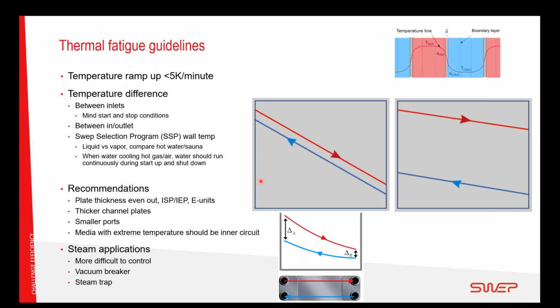We have this defined within our SWEP selection software, which is the SSP, which is used for dimensioning and selecting the heat exchanger. There we also show the actual wall temperatures, which are very different depending on what media you have. For example, if we're running a liquid to a gas, we can have a very hot air, but the liquid keeps the wall temperatures down. You can compare it to jumping into very hot water or entering a sauna at 100 degrees. One will burn you and the other one will not.